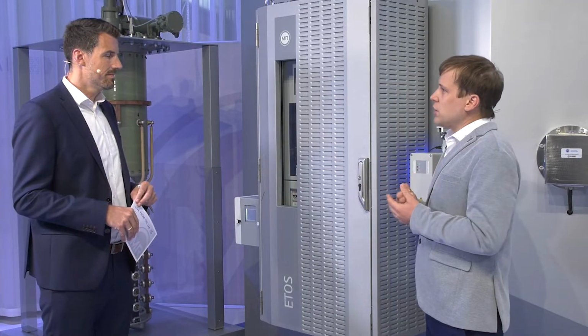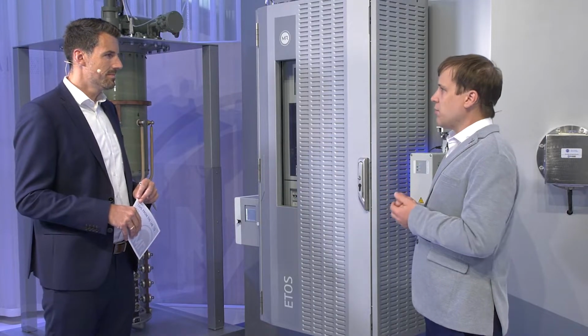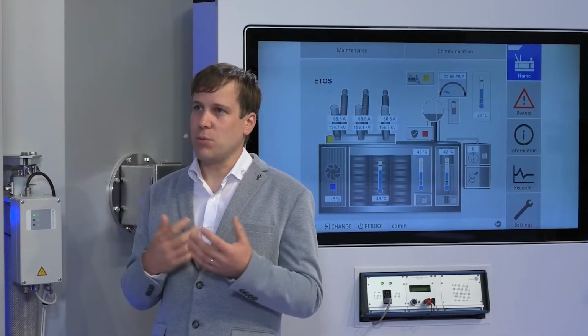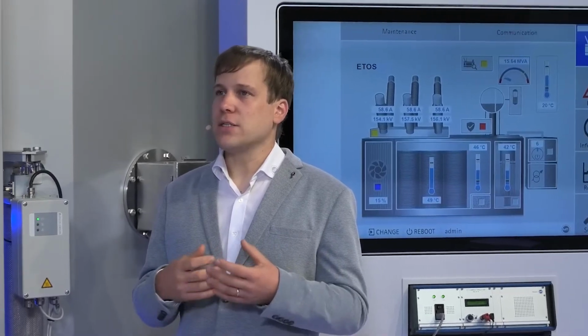So the transformer monitoring to keep track of the temperatures, hotspot, and so on, paper humidity, things like that. Then the tap changer monitoring for sure. So for example, the classic torque monitoring that we have for many years already, or the new vibroacoustic monitoring is available here. Then additionally, we can monitor the bushings of the power transformer, tangent delta, and C1 capacitance can be monitored here. And lastly, the DGA, so the dissolved gas analysis, is possible as a separate package.